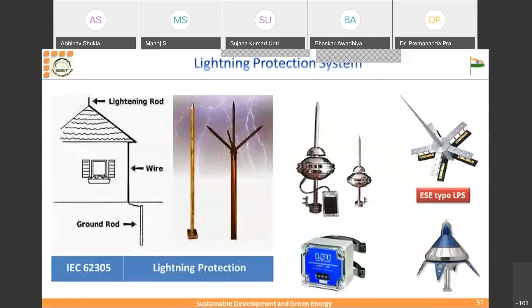This is important - you should install it at the back side of the solar plant, not in front, so that it does not cast any shadow on the plant. There is also a separation distance that is important from the discom's perspective. You should not install it right next to the plant; you have to maintain some separation distance from the solar plant for the lightning arresters.